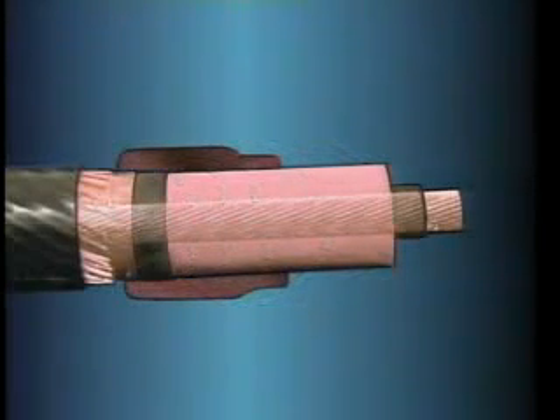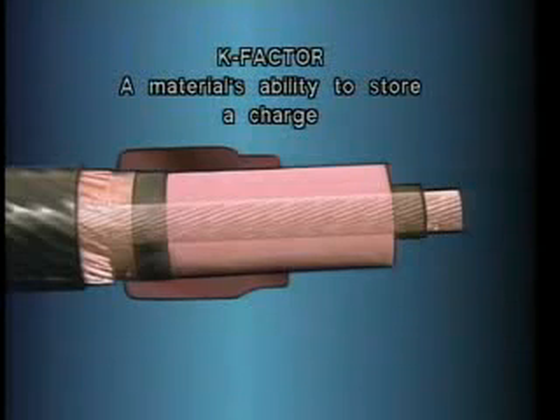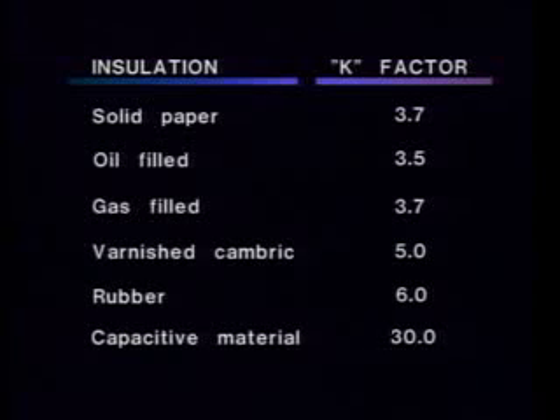Another way to control voltage stress at a termination is by applying a capacitive material over the termination area. This capacitive material has a much greater ability to store a charge than most common cable insulations. The measure of a material's ability to store a charge is called its dielectric constant and is sometimes referred to as its K factor. The higher the K factor, the greater the material's ability to store a charge. As shown in this chart, most common cable insulations have a K factor in the range of 3 to 6. The capacitive material, however, has a K factor of 30.